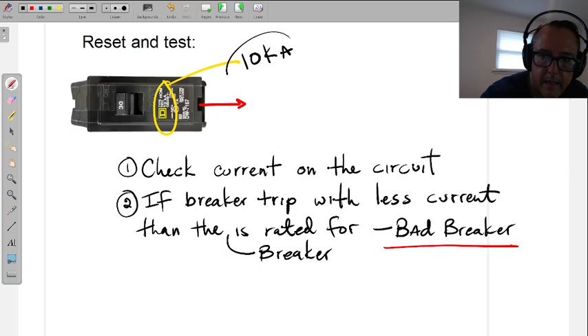Now, this is an average breaker, an average transformer outside of somebody's house. Of course, 120 is what we have inside a house, and somewhere around 6,000 amps is what's going to rush into the average home circuit during a short circuit. This is why, when I pointed out the breaker earlier, I said that the short circuit rating on most of your home breakers is 10,000 amps.